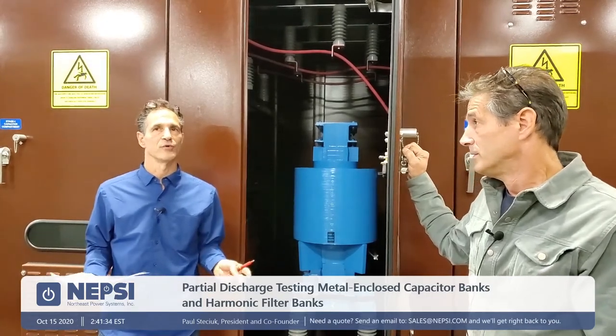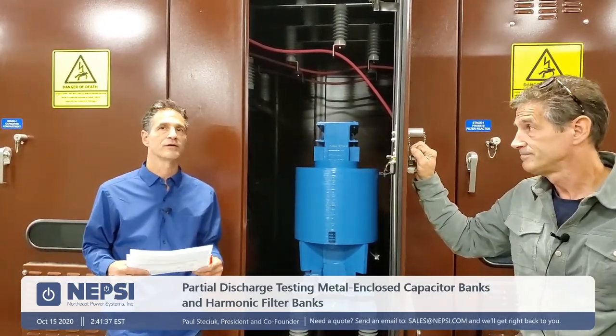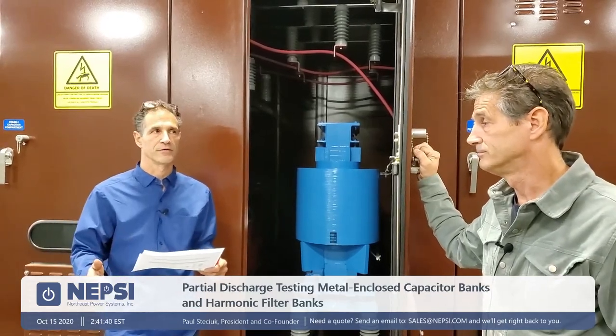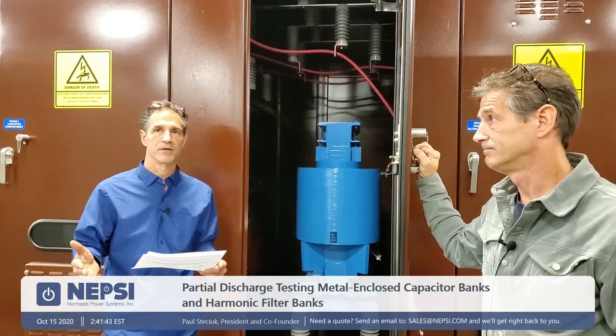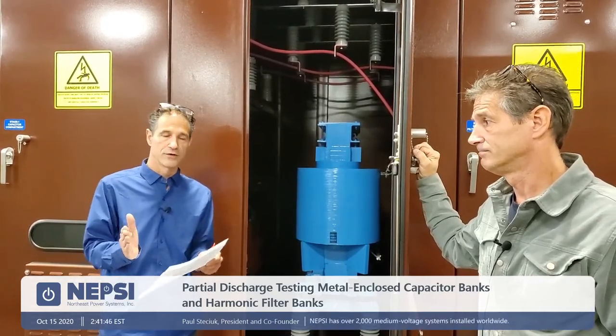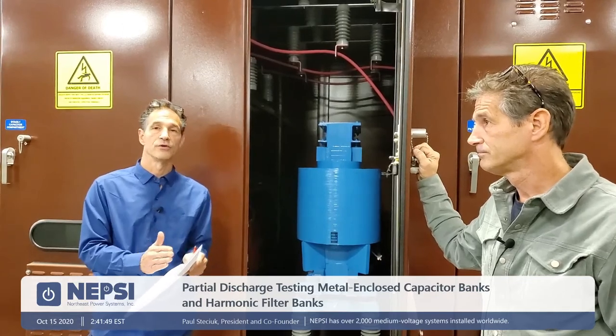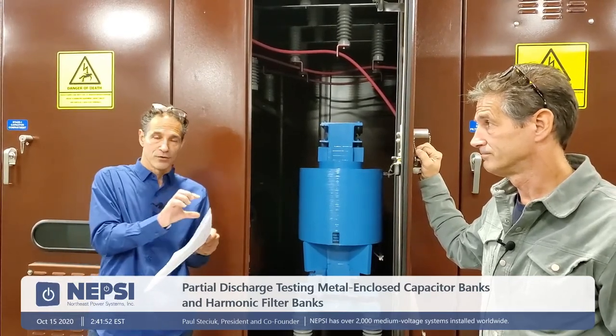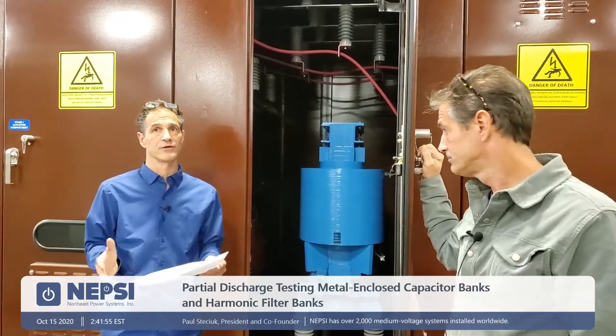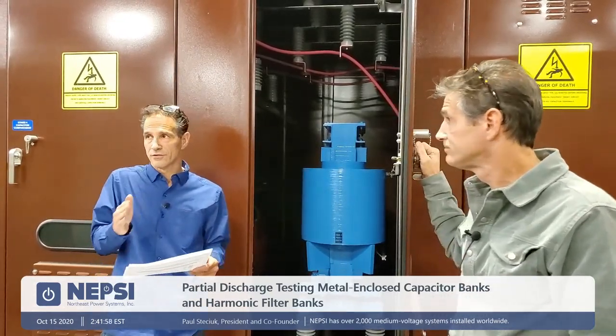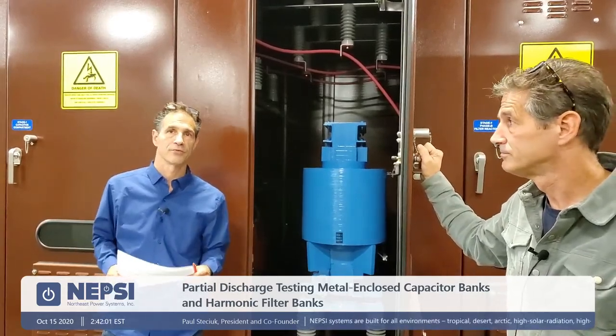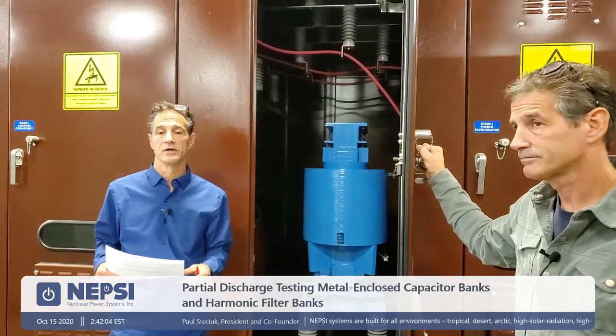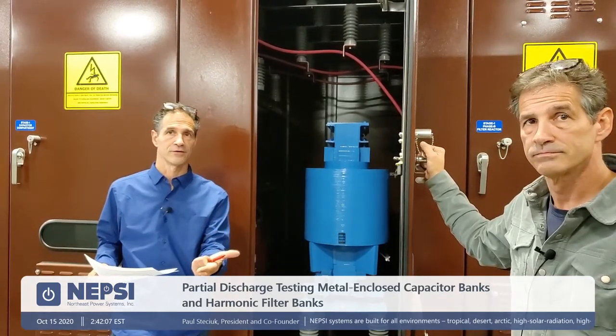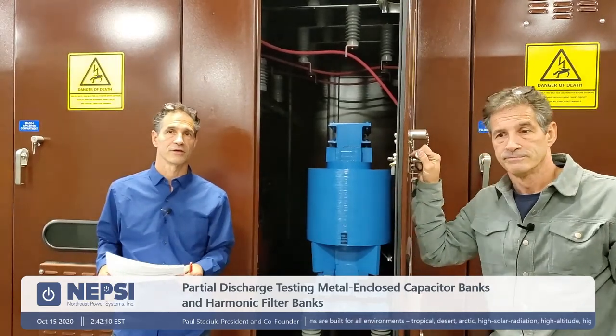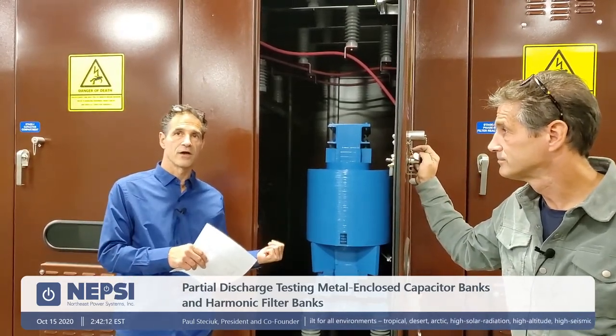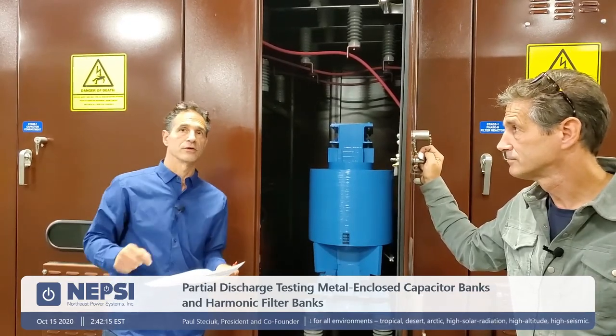So it's very interesting. What we're identifying throughout these tests is that one test may pick up one error but not another type of error. So we had a clearance issue. The impulse testing, according to what Jessica's saying here, did not pick up on that bracket being present. We did the partial discharge, and it was in the signature of that partial discharge test result that we could see that something was different, something was wrong. So we went hunting through the equipment to locate that problem, found it, and removed it. So partial discharge testing and impulse testing are two very important tests to pick up defects in the design, and also defects in the component supplies.